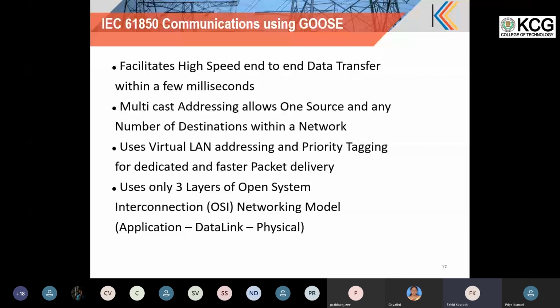Then another mechanism is priority tagging. If you want a message to have higher priority, a priority tag provision is there in the Ethernet layer. So you can put a priority tag on that GOOSE, and once this GOOSE crosses through the switches, depending upon the priority tag, it will get more preference and be sent out in a faster manner. So that is priority tagging for faster delivery. And as I mentioned, this is completely based on Ethernet. So the GOOSE application layer, data link and physical will be using Ethernet.